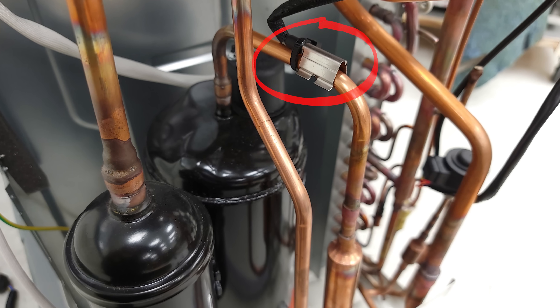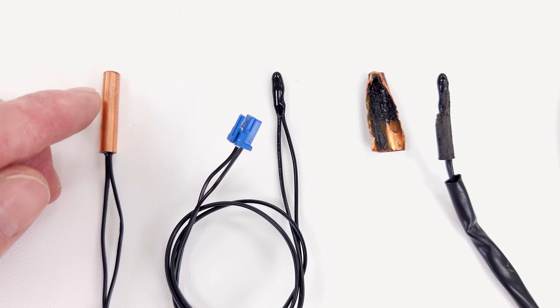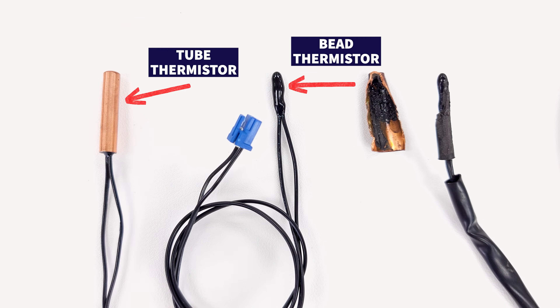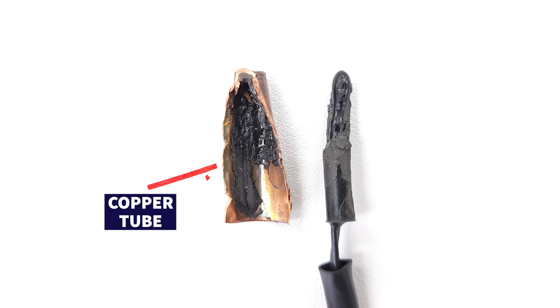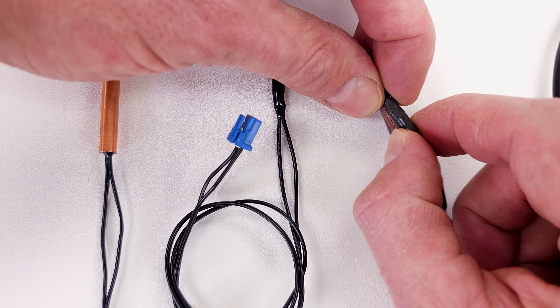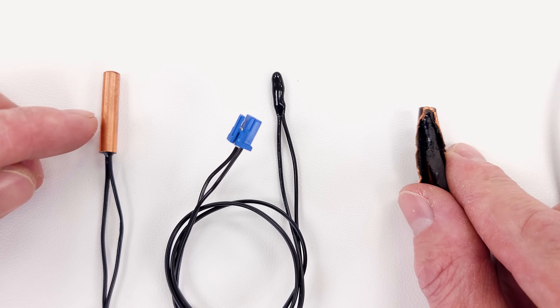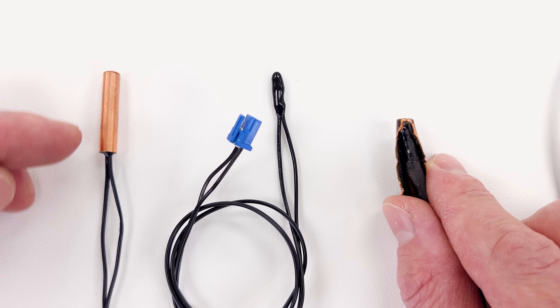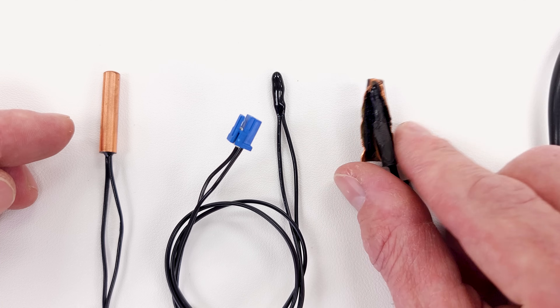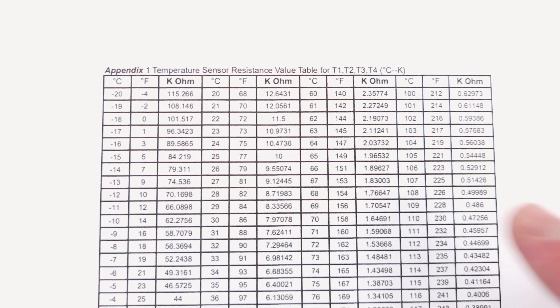There are at least five thermistors on every single-zone system, and on multi-zone systems you'll have a lot more. The difference between a tube thermistor and a bead thermistor is really just that a tube thermistor is a bead thermistor mounted inside a copper tube — that's about it. You have this epoxy-coated NTC thermistor inside, held with a little rubber epoxy. The tube thermistor has increased surface area so it takes slightly longer for resistance to change with temperature, but essentially they're the same.